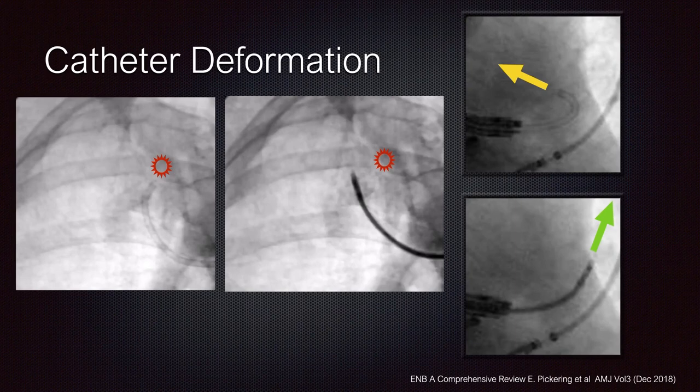With standard ENB, to achieve targets in different areas we used very pre-bent, pre-contoured catheters. With enough wiggling we could get on target, but then when we passed regular biopsy instruments — brushes, needles, forceps — we developed catheter deformation. There I am on my virtual target, I know I'm there, I may or may not have a bronchial sign, I've taken 10 or 20 biopsies and I'm getting normal lung parenchyma or benign bronchial tissue. There is a real component of deformation that occurs with these pliable catheter systems.